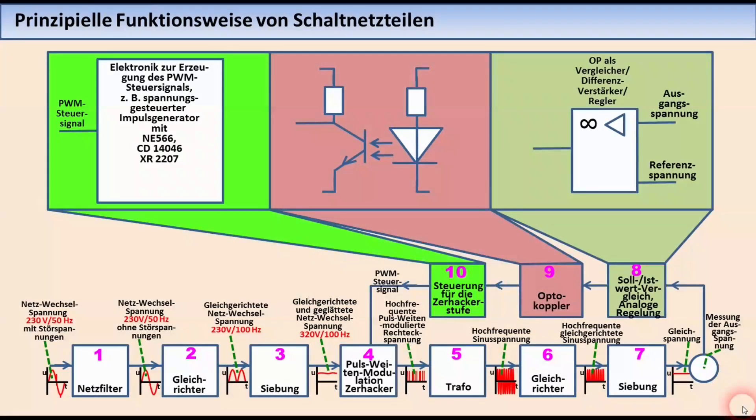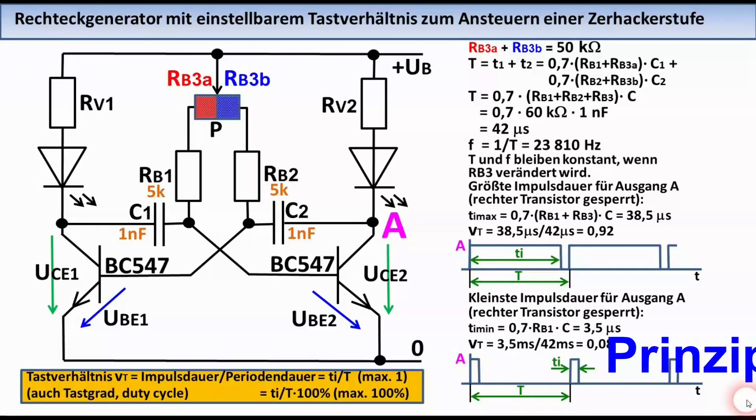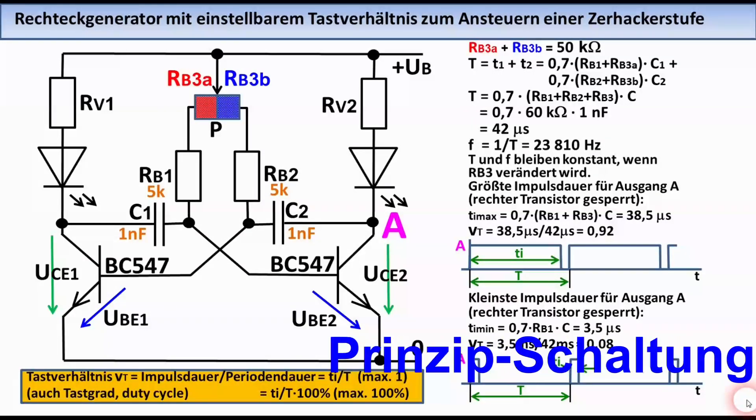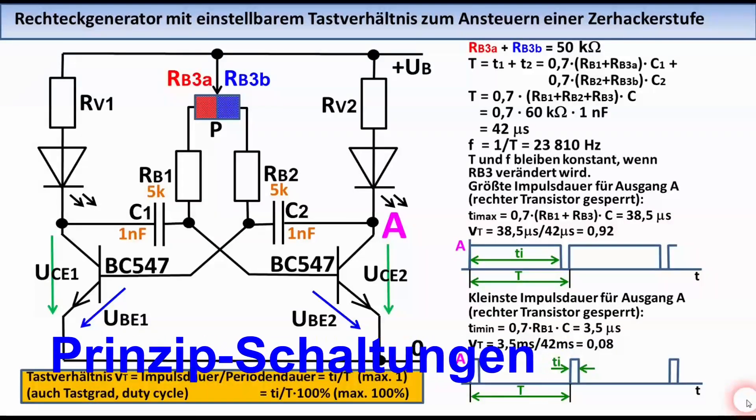In Abhängigkeit vom Istwert-Sollwert-Vergleich erzeugt dieser Baustein ein Signal, das dann über den Baustein 9, nämlich den Optokoppler zur Potentialtrennung, dem Baustein 10 zugeführt wird. Der Baustein 10 erzeugt dann wiederum ein Signal zur PWM-Steuerung des Bausteins 4.